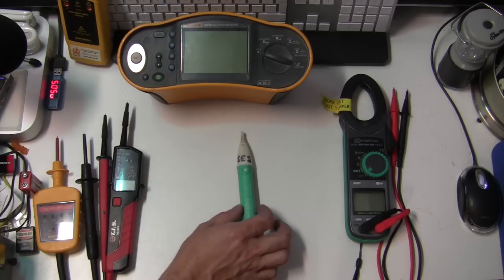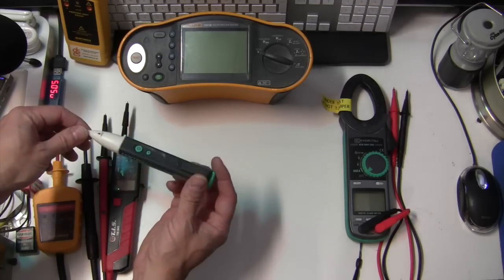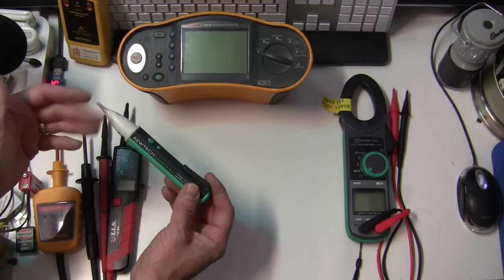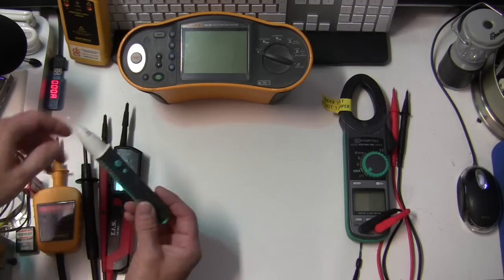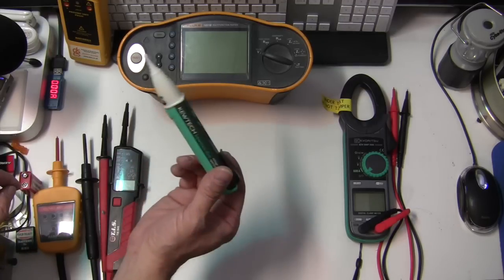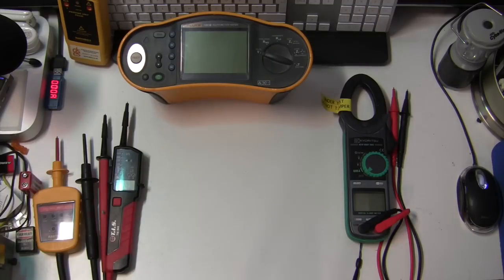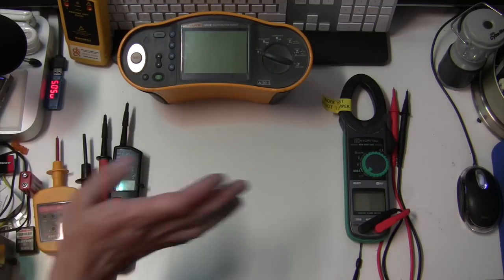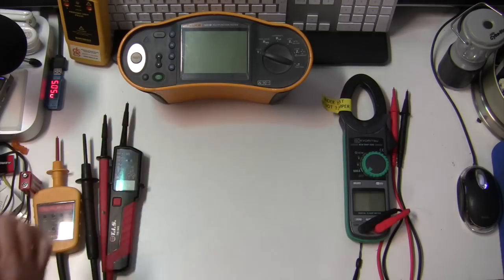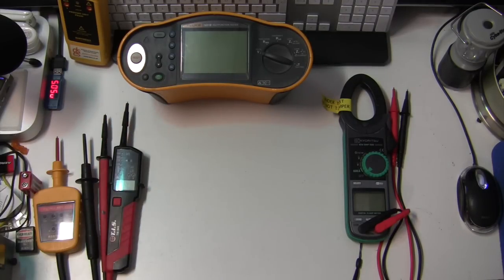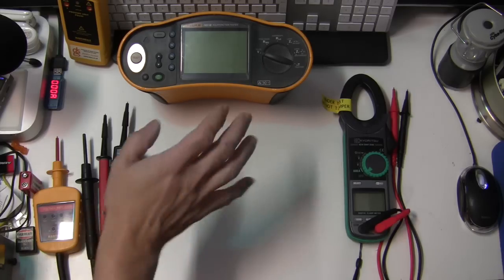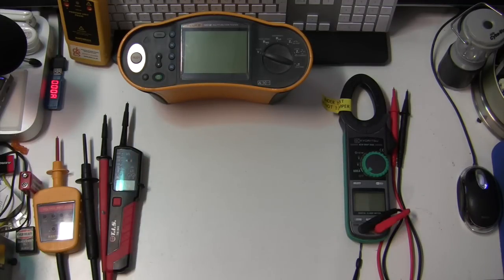A non-contact voltage indicator like this has no place in safe isolation. These are merely a basic tool for indicating that a cable may be live—you can't rely on one to prove anything is de-energized. Similarly, a multimeter or multifunctional tester is also not valid for the job, at least not for your competent person's assessment, because it's too easy to select the wrong function and get a false result.